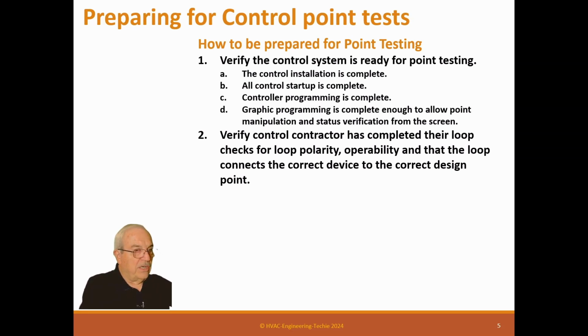One of the things you've got to watch out for is that in the control world, a lot of times they have canned sequences or canned graphic plates, and all you have to do is change the device name and it changes all the points automatically. Or sometimes you have to do that manually, so it's something you have to check, because if the points were not brought over correctly or were manually input wrong, what is the supply sensor on fan coil 1 may not be the supply sensor on fan coil 2. You have to check those to make sure they're correct. There's a lot of things you can find when you do point testing.